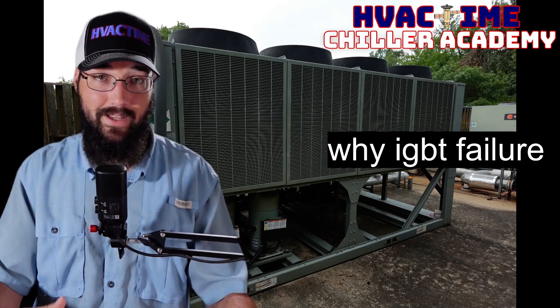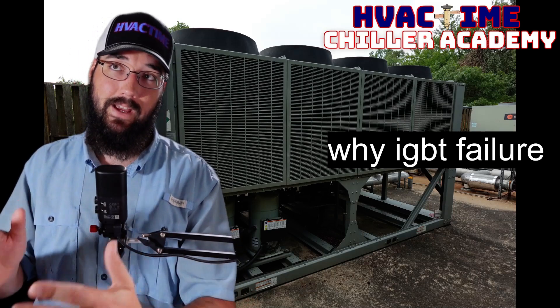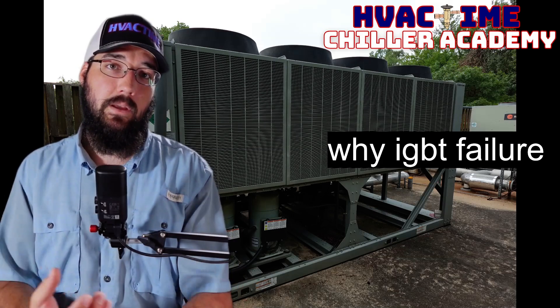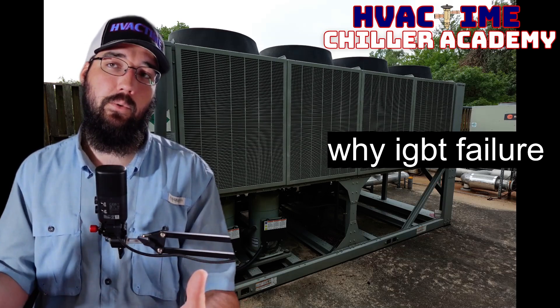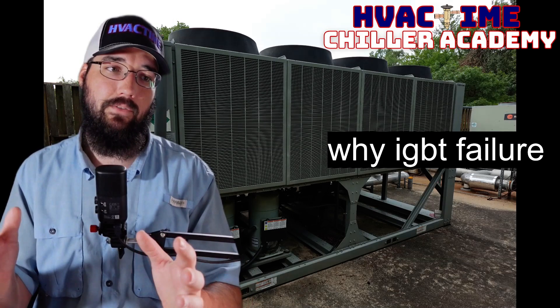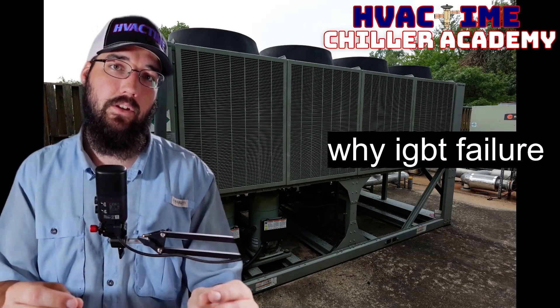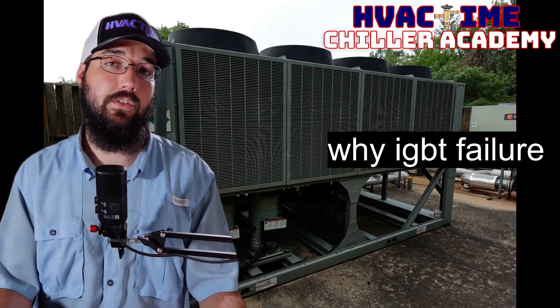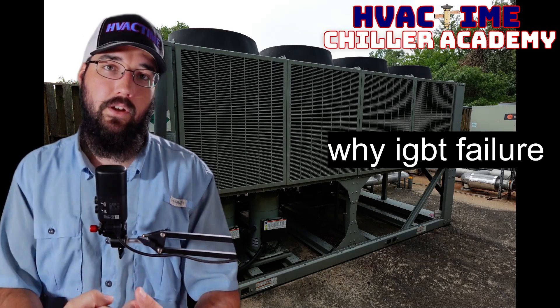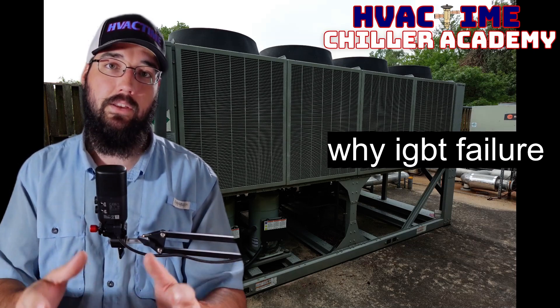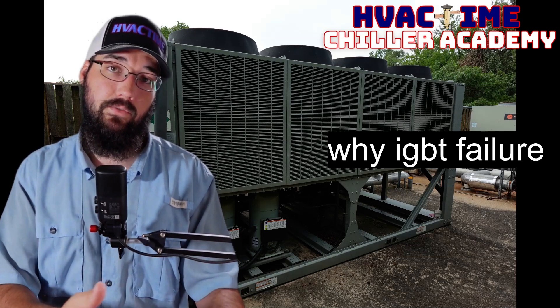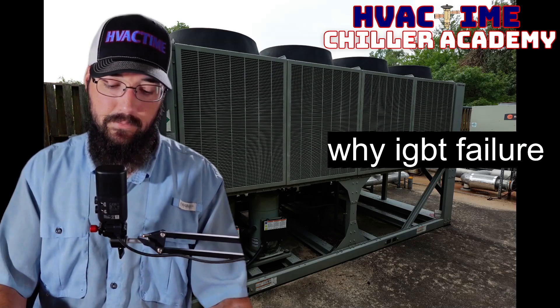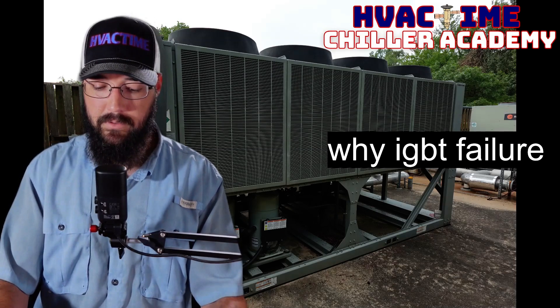Another way I've tested this is if I've had a system where I had multiple compressors, I would actually sometimes swap the gates out. Or if I had multiple chillers there, like if I really thought this was the case, and the customer wanted to for sure know, not just go off of my best assumption. I would take one of the other IGBTs, put it in its place, and we would run test it and see if the compressor sounded better. If it did, we knew for a fact that that IGBT or that inverter needed to be taken care of.